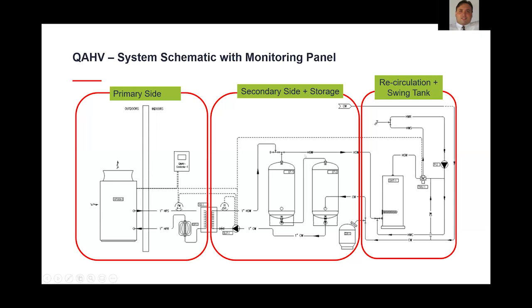And so what you'll find with most manufacturers, including Mitsubishi, is they want to be directly involved and in control of these primary side and secondary side and storage components, because those are all paramount to proper operation of the system and achieving and maintaining the domestic hot water demand that's required for the building. The recirculation and swing tank side, again, that's fairly common on the recirc side for most building designs. Many manufacturers will offer options for swing tanks. We do as well, but those aren't required to be typically procured from the manufacturer.